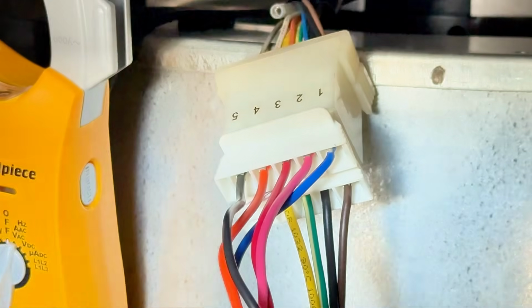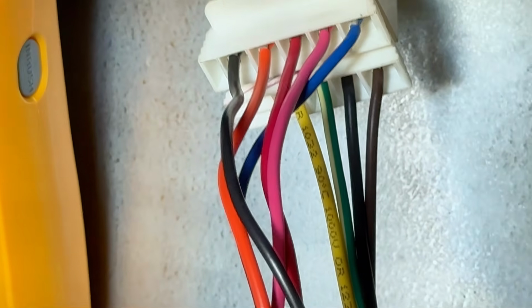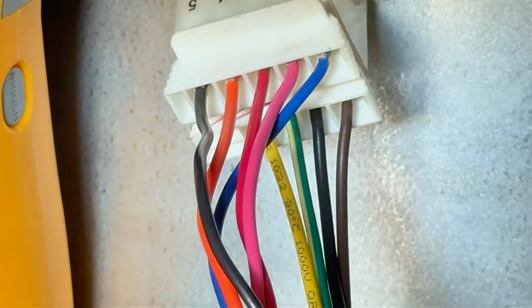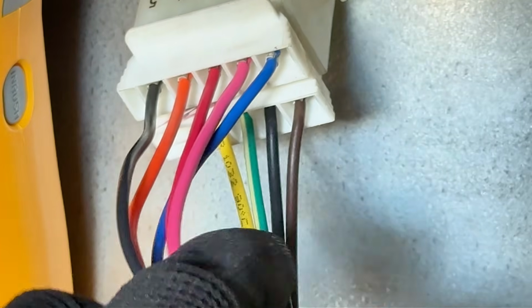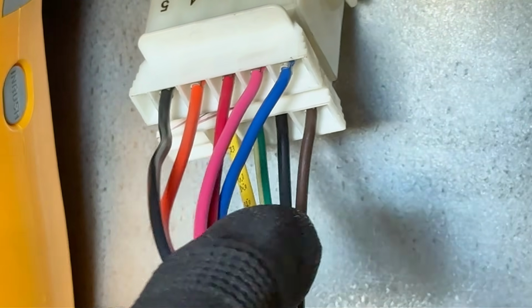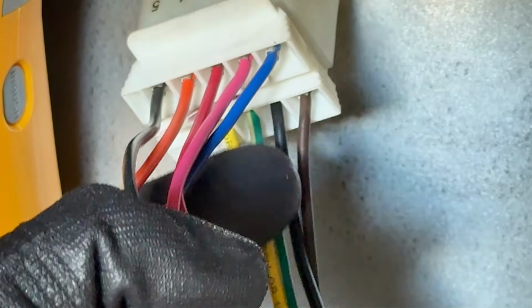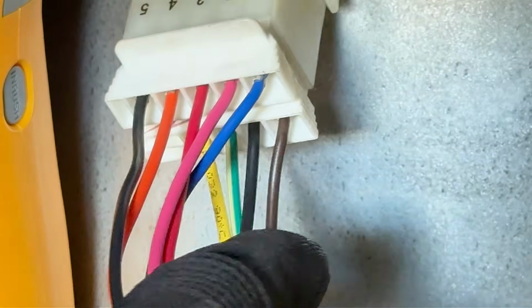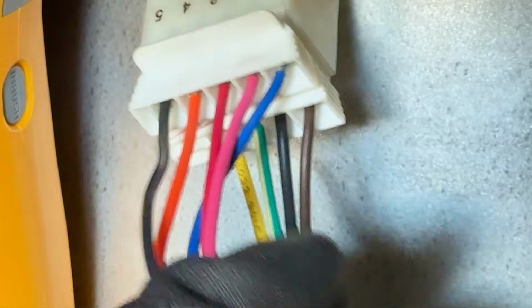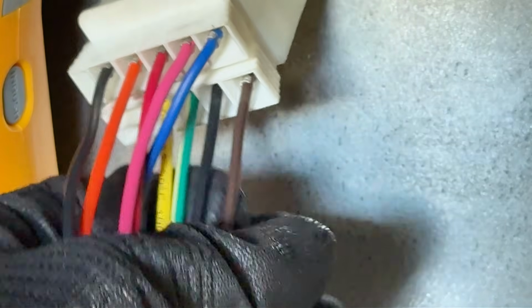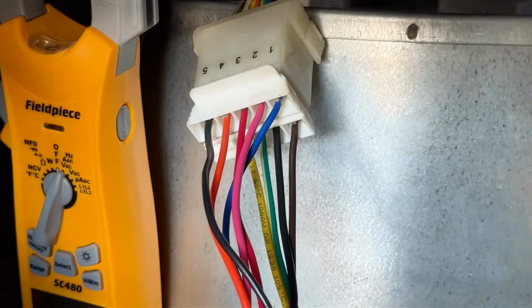On the bottom right here, let's go ahead and zoom in a bit more. On the bottom, you have your high voltage. So your yellow, you see that? Your yellow and your black, that's your 208 high voltage. The green one is your ground, and the brown one is your common. Just like this is 24 volts, the brown one is your common, okay? So let's go ahead and check that.